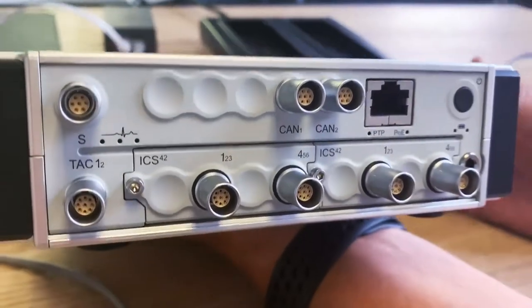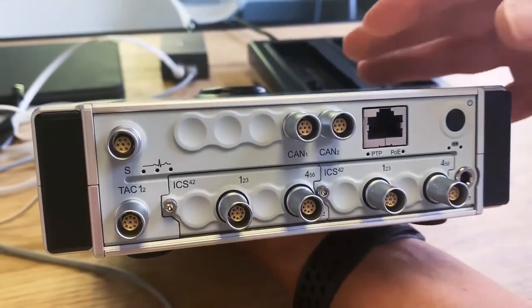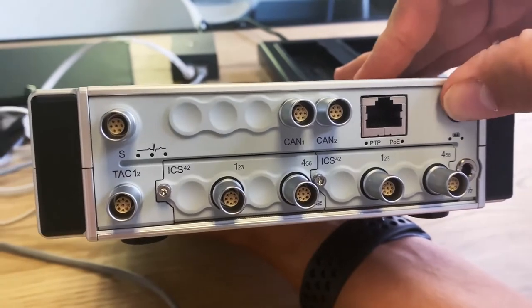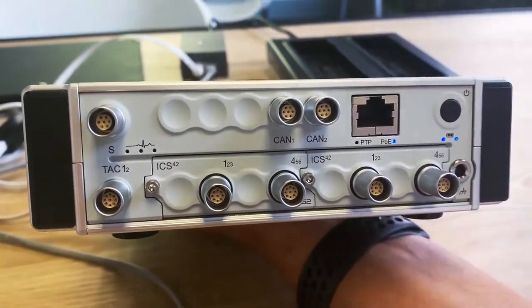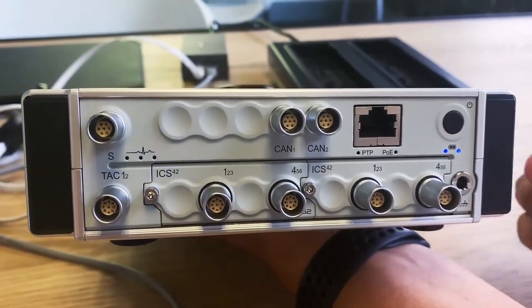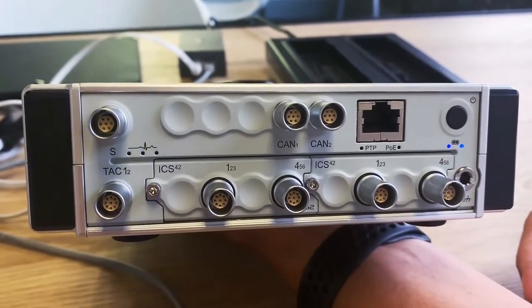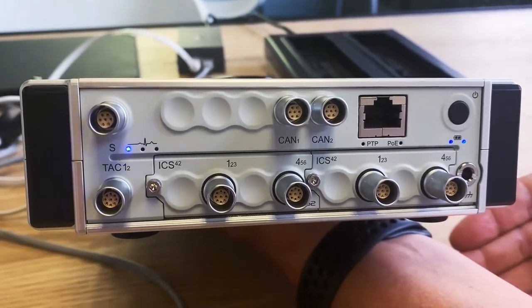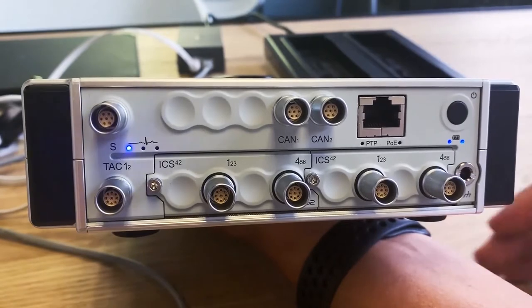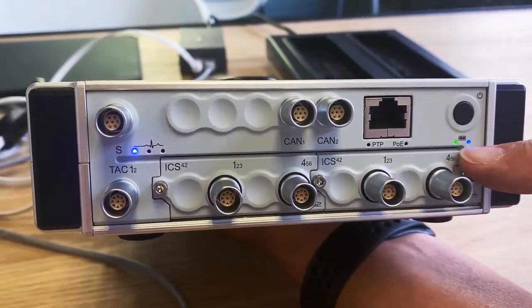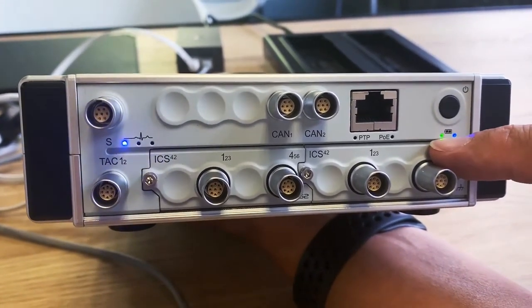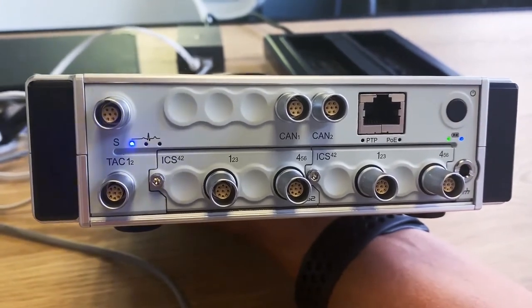Now we're completely on battery power. When we go to start the MICROQ, it'll give us an indication of not only the available battery, but the battery that's currently being used, as well as the status of the batteries themselves. And that all comes through these two indicators. Now we can see we're using internal battery with the external battery available.